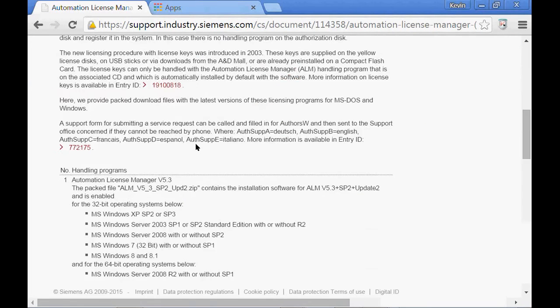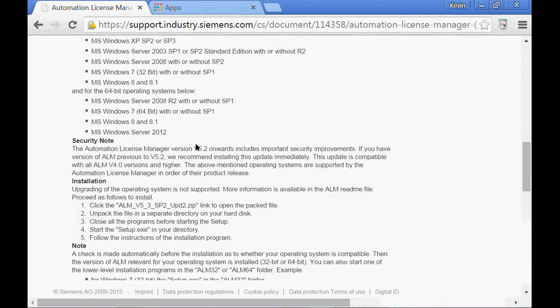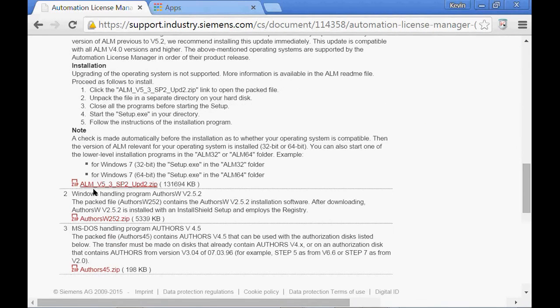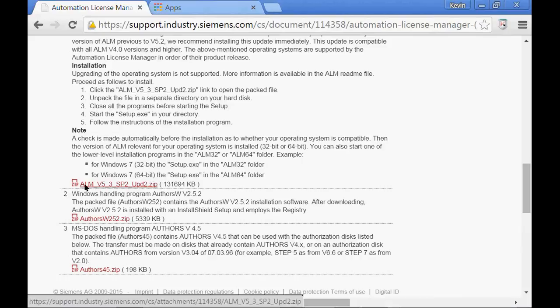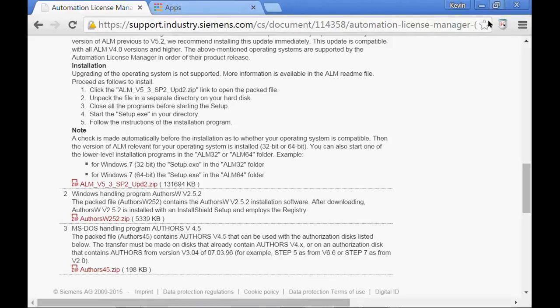If you scroll down, you will see a link to a zip file. The latest version is Automation License Manager version 5.3, Service Pack 2, Update 2. You want to download that file, unzip it on your machine, and install Automation License Manager.